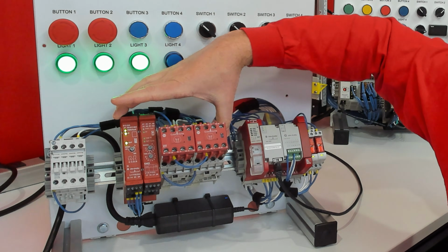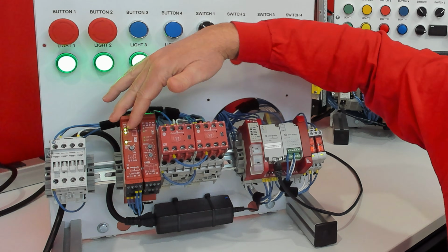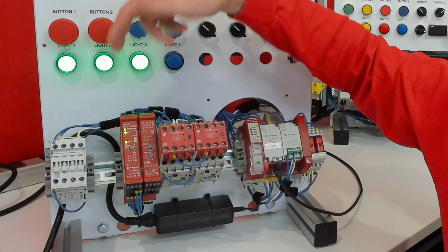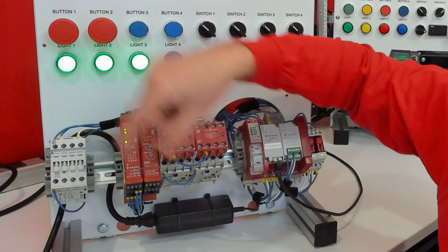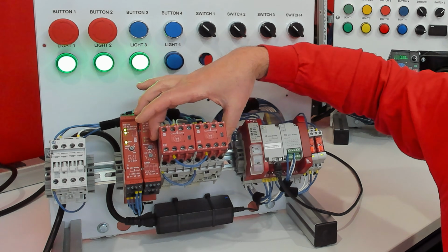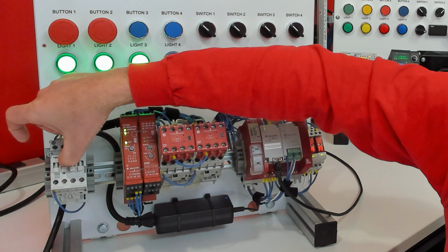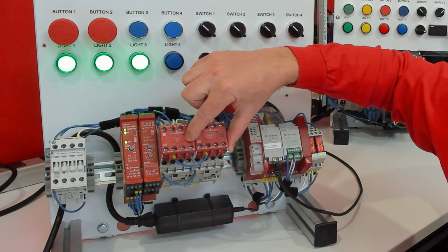And then we have our non-configurable safety relays. Sometimes these are yellow, sometimes they're orange, but typically you're going to have two contacts on your E-stops going down to these. And then you're also going to have two contactors in many cases on the outside of them. And even in this case where we could push this contact in, notice these have windows here to prevent us from overriding them.